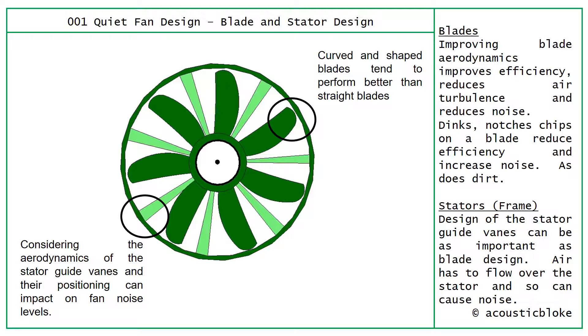Improving blade aerodynamics improves efficiency and reduces turbulence, which reduces air noise. Dinks, notches, chips and dirt on a blade will reduce its efficiency and impact overall noise level. So if you're looking at an existing fan system, it's worth checking that the blades are in good condition. We're concerned with ensuring a good level of balance in the system, as these defects affect balance, and when things run out of balance they have a tendency to make more noise.